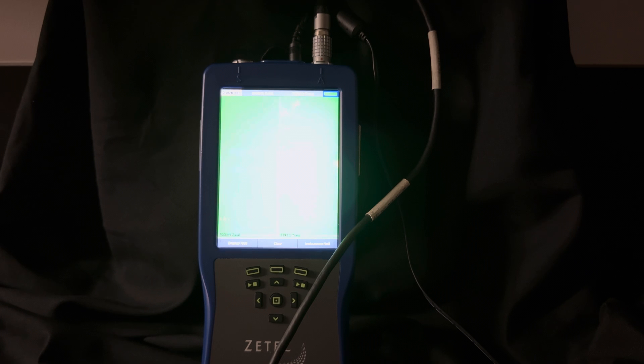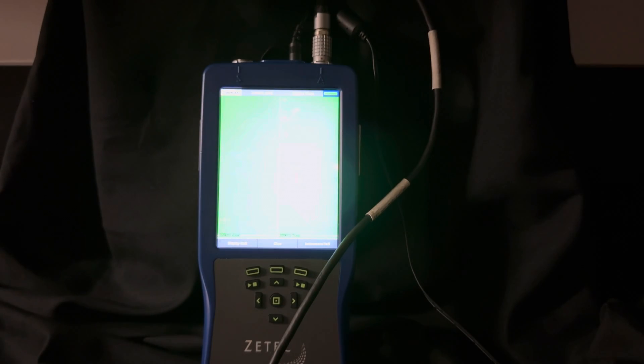You can tell if there's two flaws next to each other, how much space is between the two flaws, things like that. So you get a lot more information with the array probe. Higher POD because there's less chances of missing flaws.